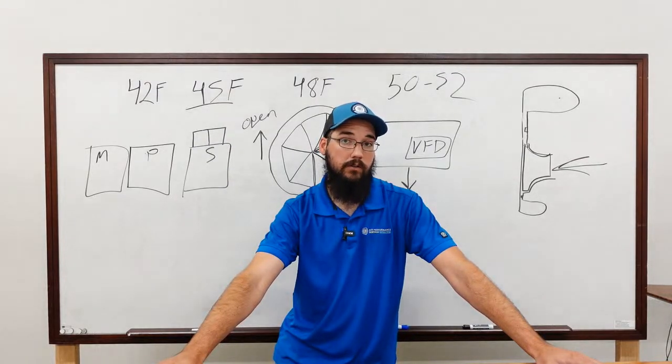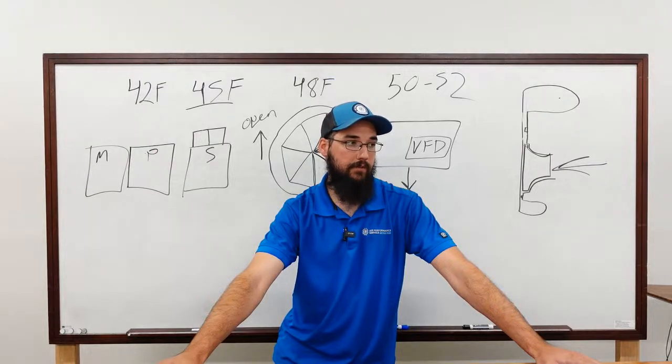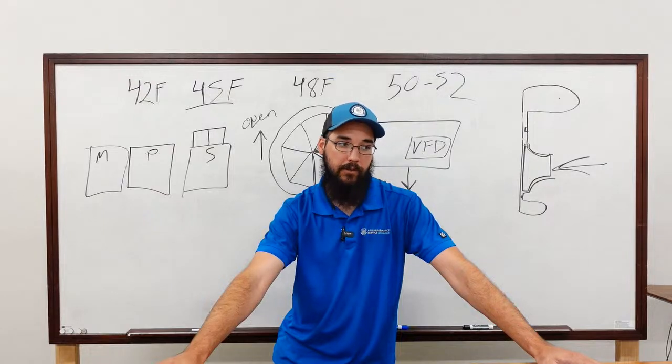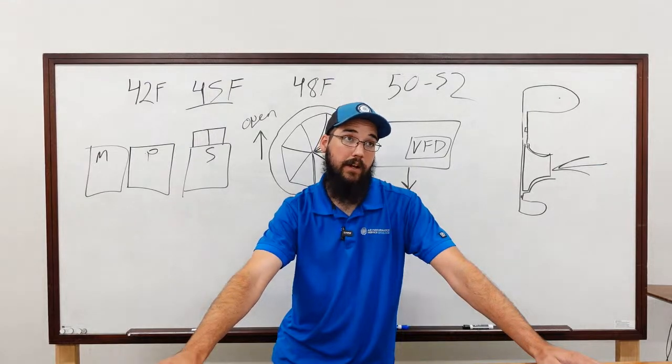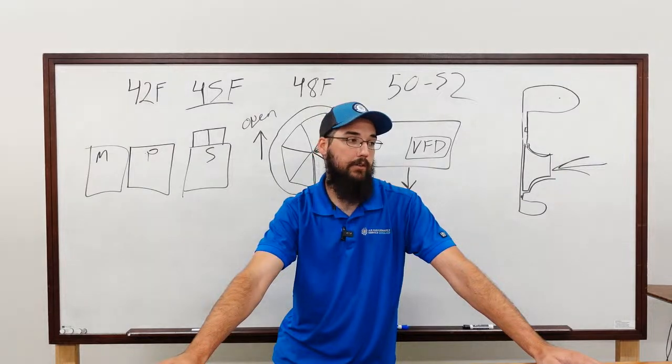A York, I would have been surging a long time ago. Not a knock on York, it's just a different design. They have a different approach to theirs. So for a York, with those same design parameters, I'm probably not going to get that thing to run much above 85. That's 85 entering water, not leaving. That would be something I would expect, something along those lines.